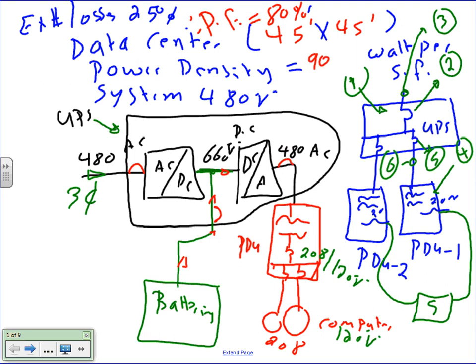Why do we do a system like this, guys? Because on the DC level right here, you are always tied. You have 2 sources of power tied, synchronized at all times. So if you were to lose this side, you don't have to switch. The battery here will take care of business for 15, 20 minutes. So you would never see any interruption in the power. Cool? That's why they have the UPS system. Any questions, guys, about how the UPS system works?